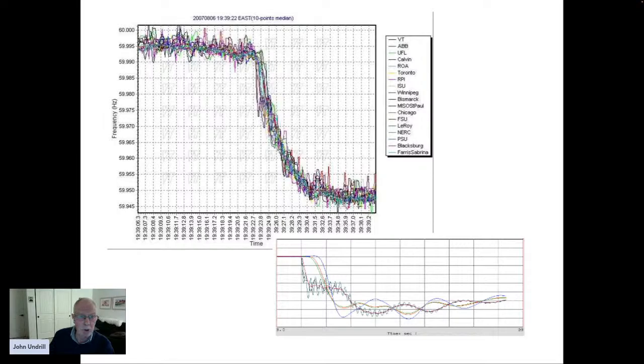There are many machines here sizzling, but all rotating at a common speed. This is a sizzle that I talked about before. This is a simulation of the Western grid when a large block of generation was lost. And you see frequency changed very rapidly when a small event occurred first. And then when a larger block of generation tripped about 2 seconds later, frequency went down. And again, it sizzled, but you can look at the mass of the system and say it goes like that.